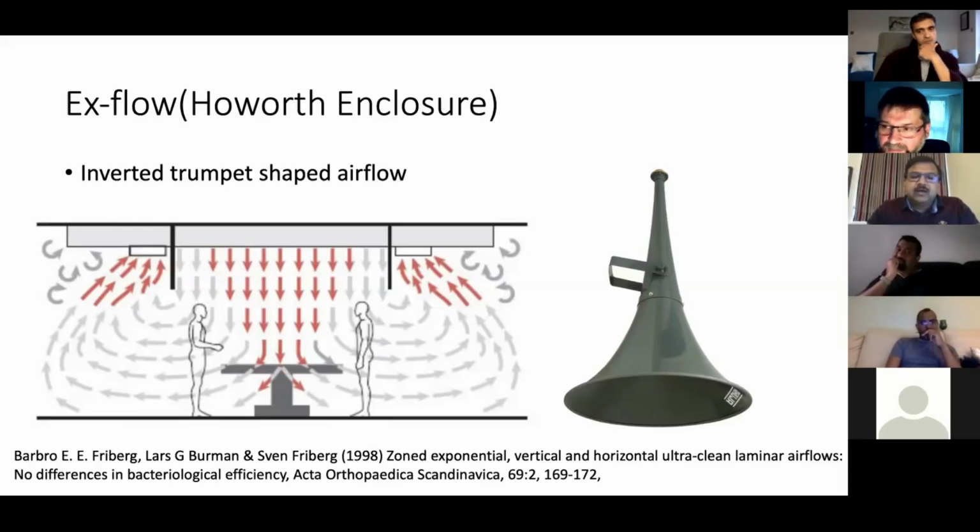But in essence, what actually happens is there are so many things which affect the flow of air. One of the important things is we have ceiling mounted lights. The canopy of the light covers the laminar flow in an area, so the laminar flow gets obstructed by it and then reforms, but it does not stay as non-turbulent as it should be.